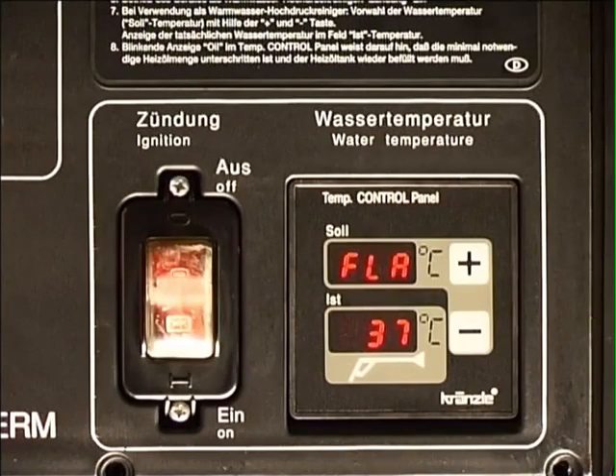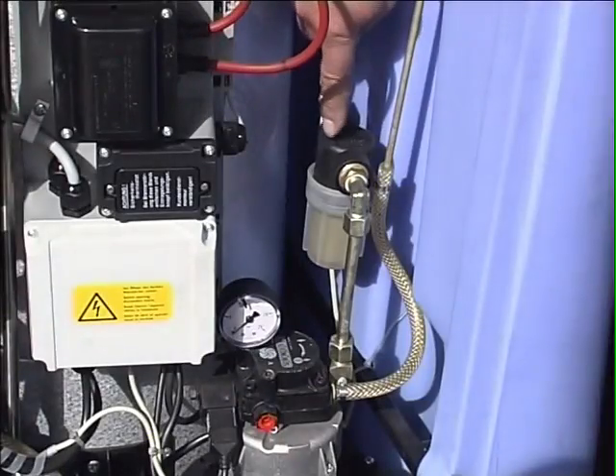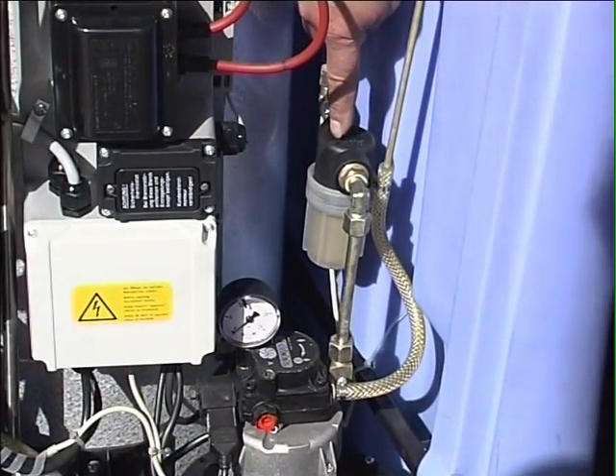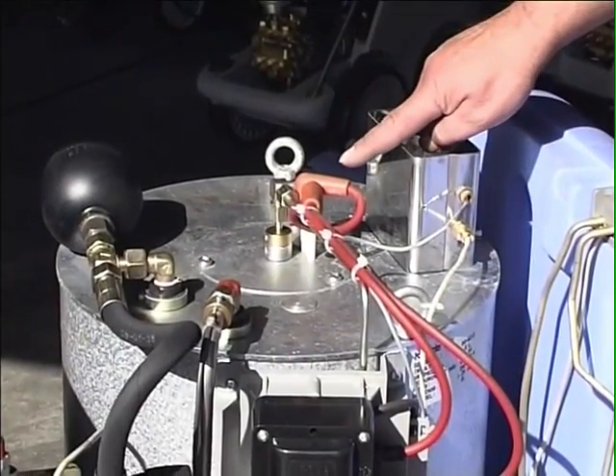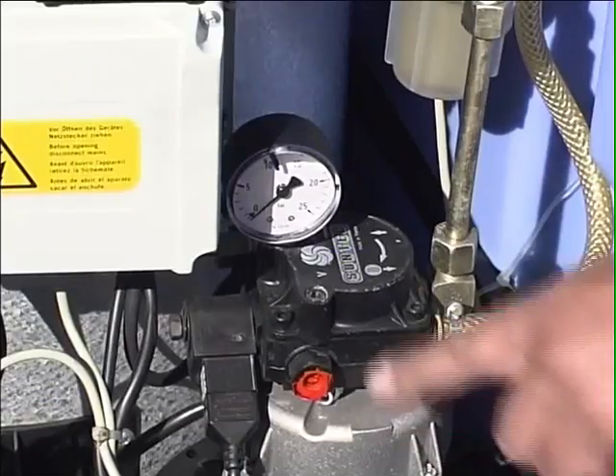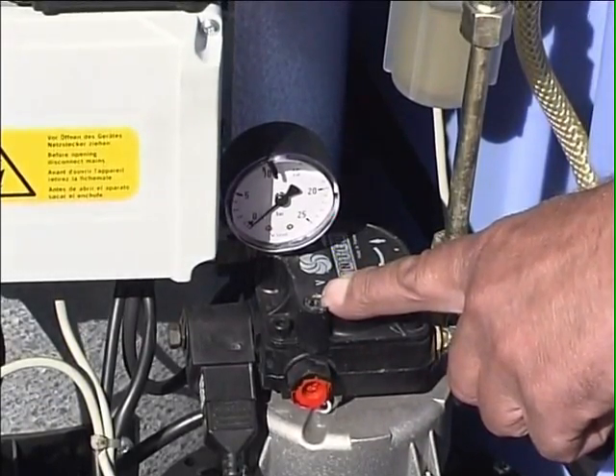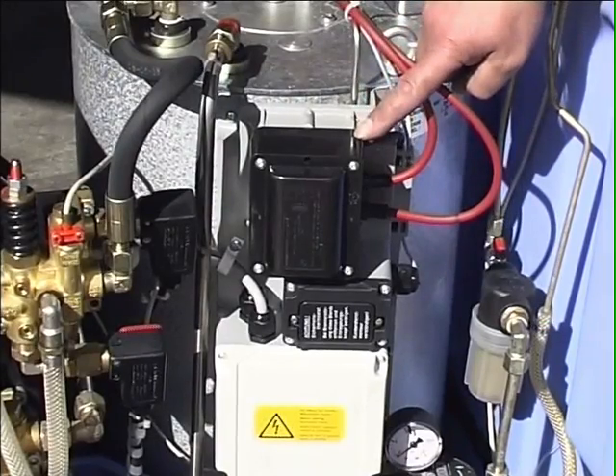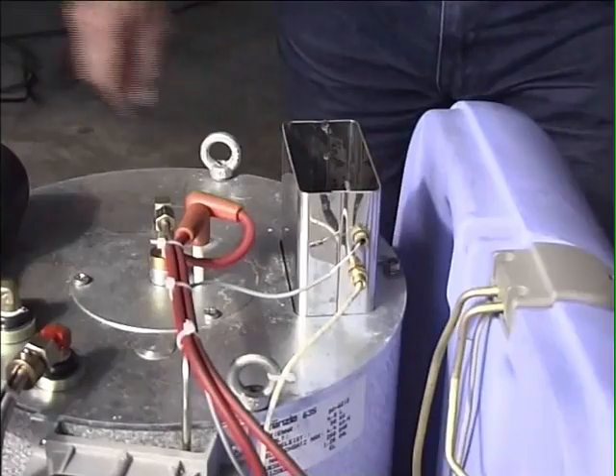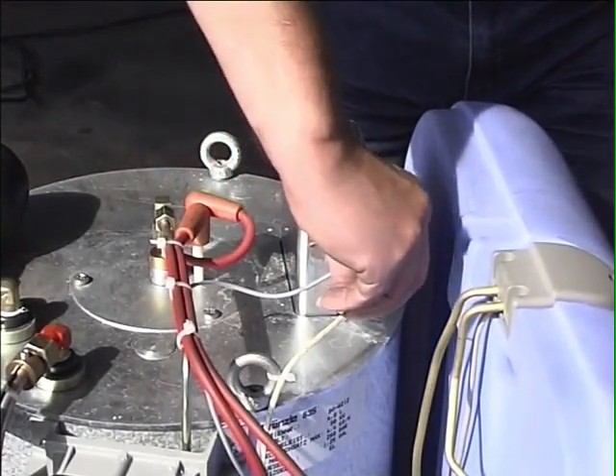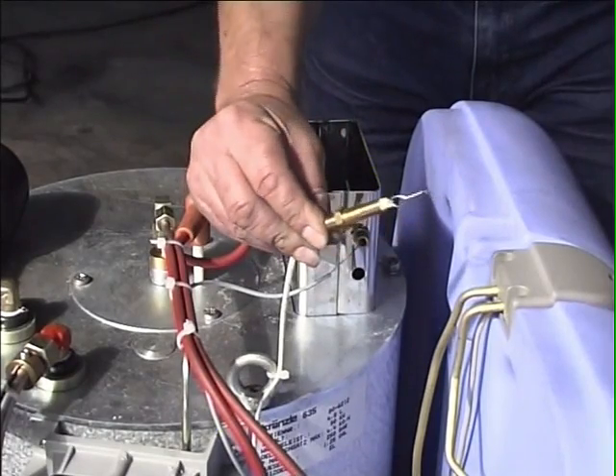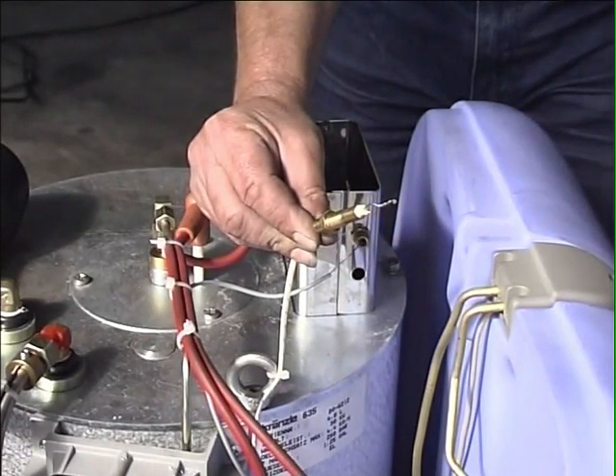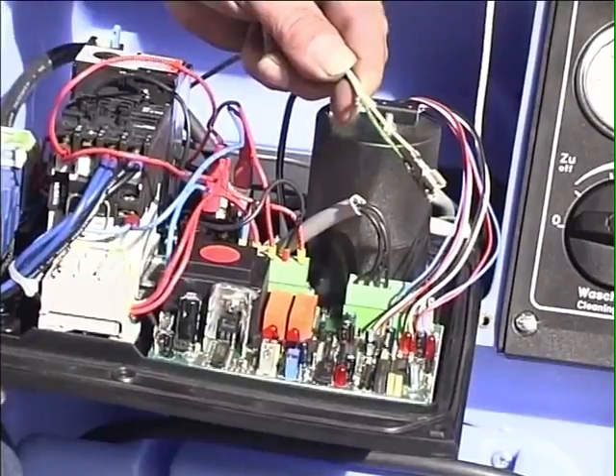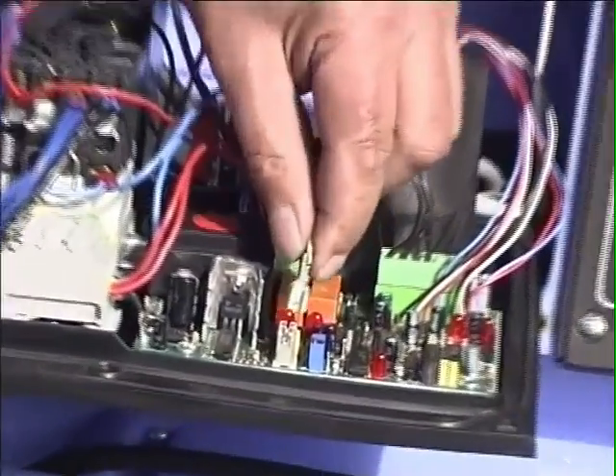The error message FLA lights up. This means that the burner cannot start. Check the fuel filter, ignition electrode, fuel pump and solenoid valve, ignition transformer and this temperature probe for the flame monitoring. Once you have replaced the probe for flame monitoring, watch out how you insert the contacts. White on the outside, green on the inside.